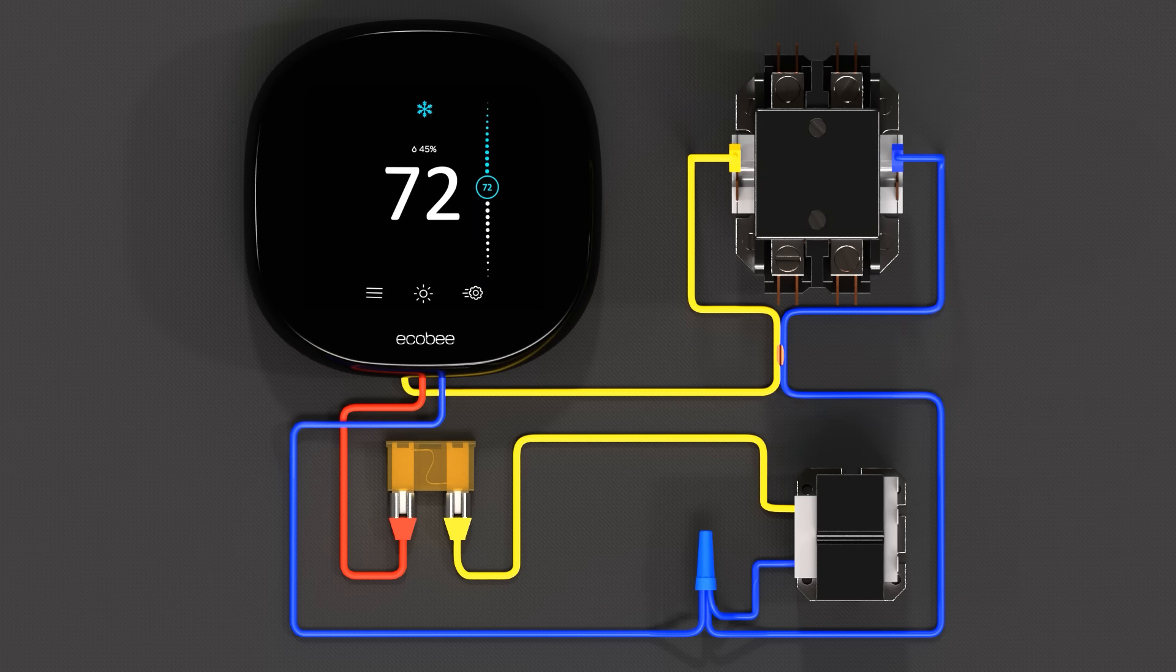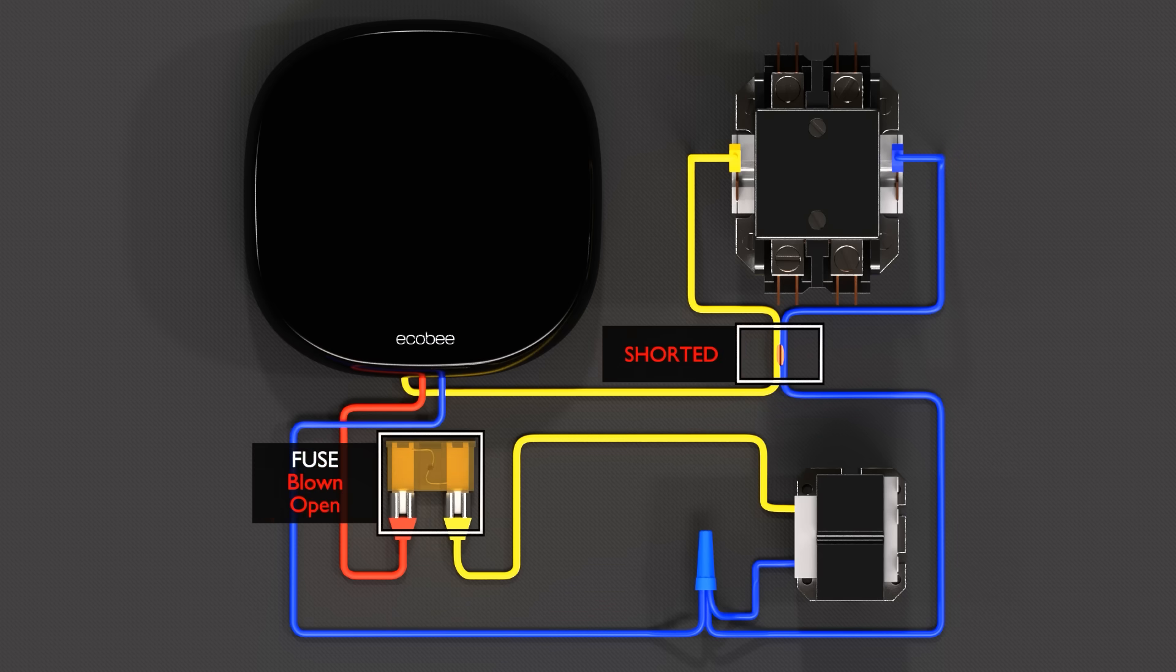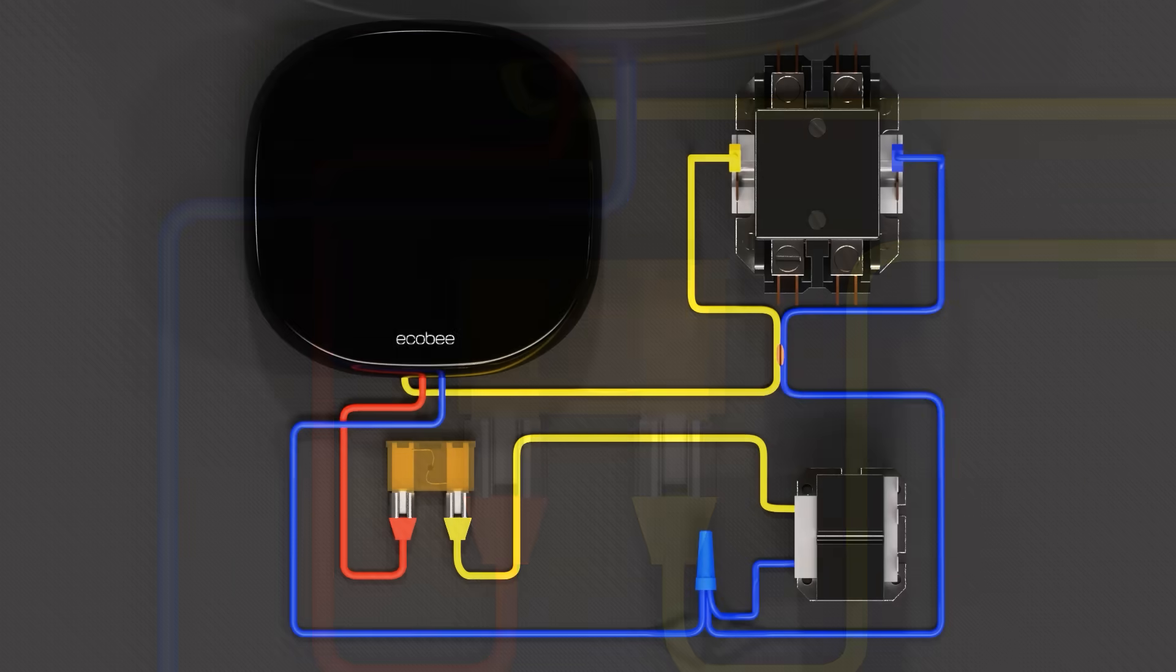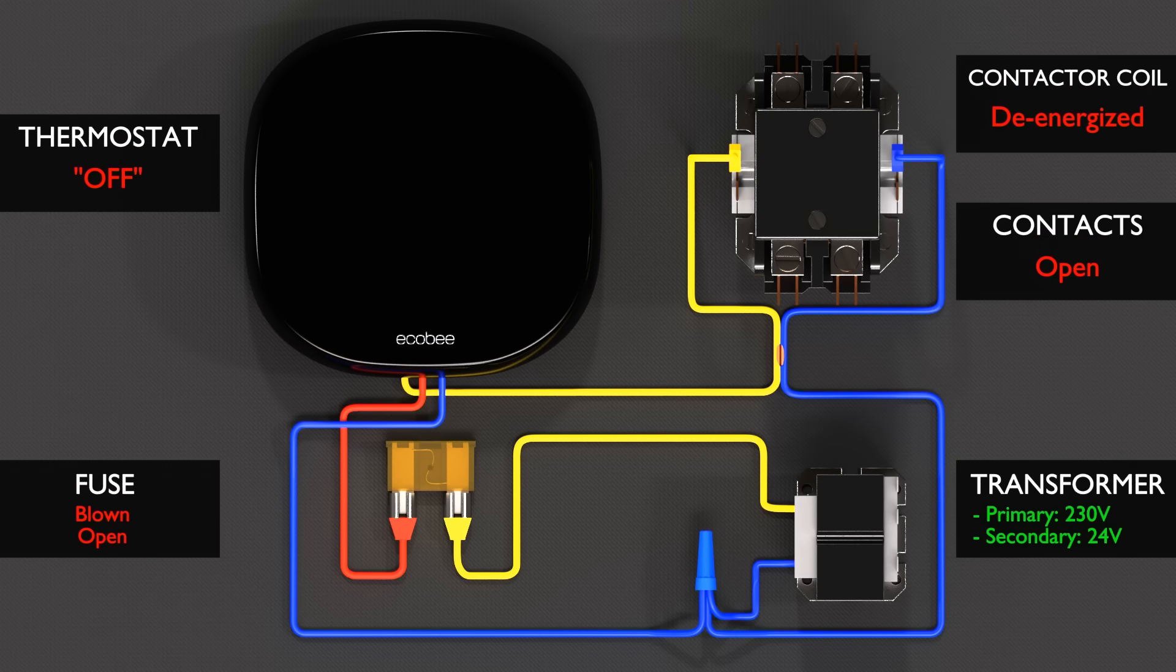A short circuit, or a dead short between hot and common, will result in a blown fuse. This is because the electricity is allowed to travel, bypassing the load, making this circuit shorter than it should be. This short causes a high current, which forces the 5-amp fuse to blow, protecting the circuit. Because the fuse is blown, or open, thermostat will now be off, the contacts will be open, and the contactor coil will be de-energized.